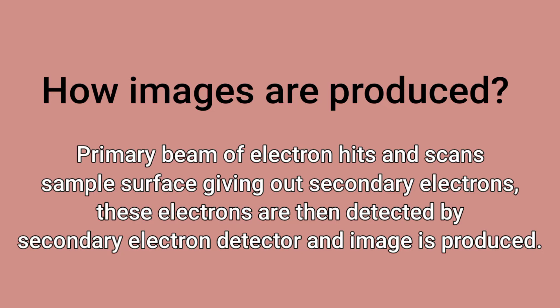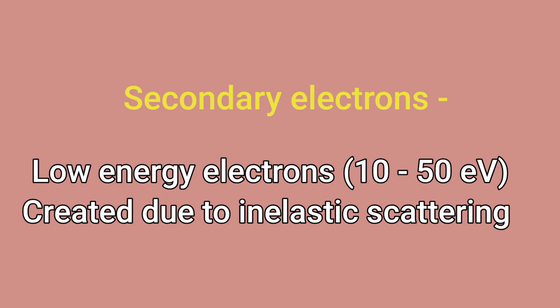How do secondary electrons differ from backscattered electrons? Secondary electrons are considered low energy electrons, having energy in the range of 10 to 50 electron volts, and they are created due to inelastic scattering of electrons. Secondary electrons give valuable information about the topography of the sample.